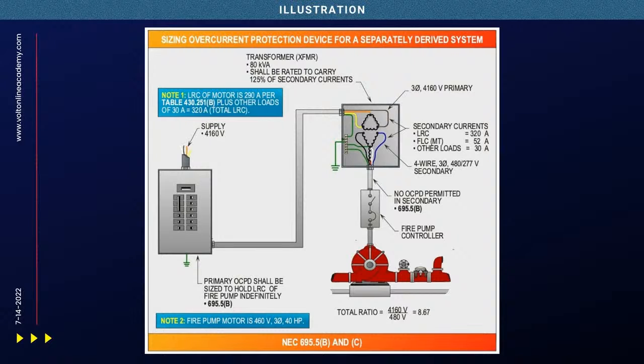Now, this is where I'd be setting up and doing a buck boost here and kicking it up with a transformer. In other words, instead of doing voltage drop here, we put a transformer in here. Dude, that satisfies the language. Yeah. Nice. And what you'll see here is I've got an 80 kVA transformer, and it'll tell you here, shall be rated to carry 125% of the secondary currents. And we're going to look at this in just a minute.